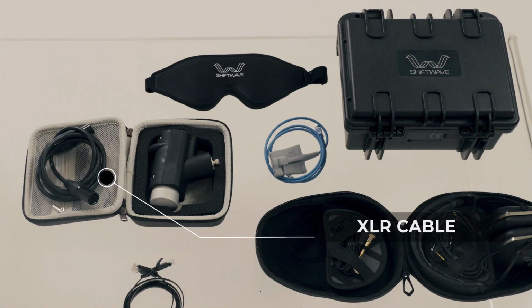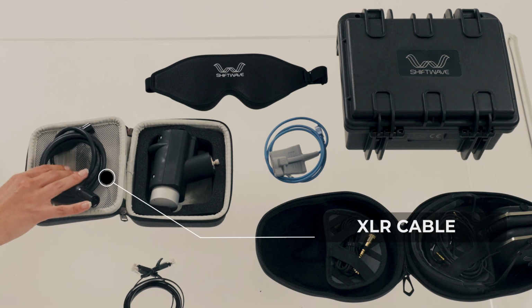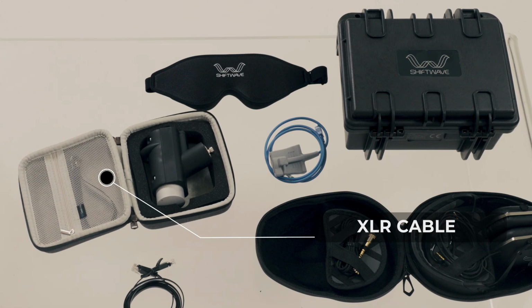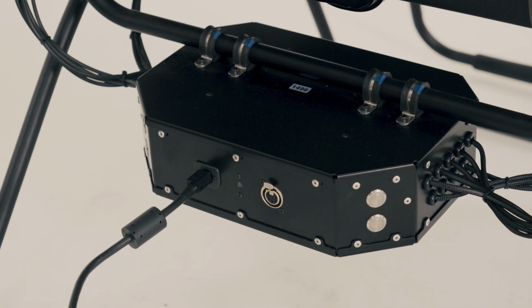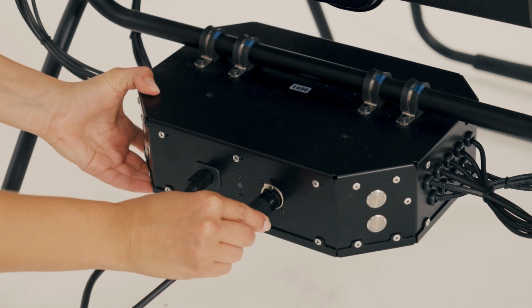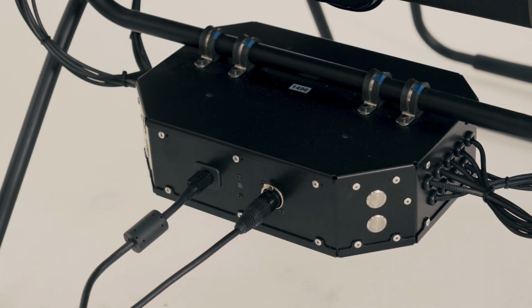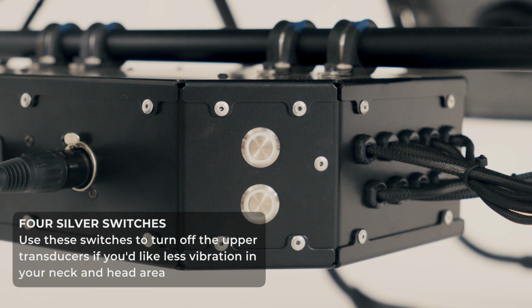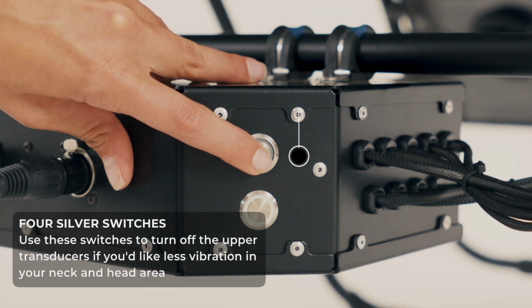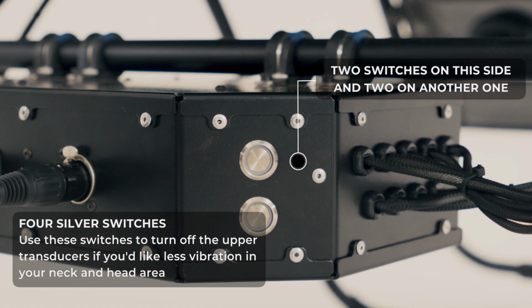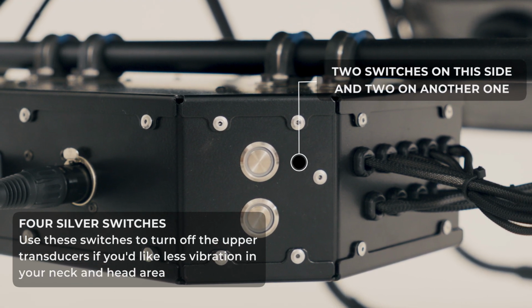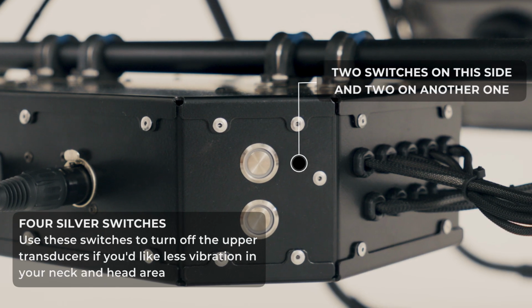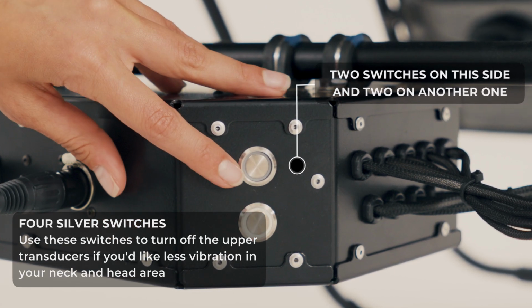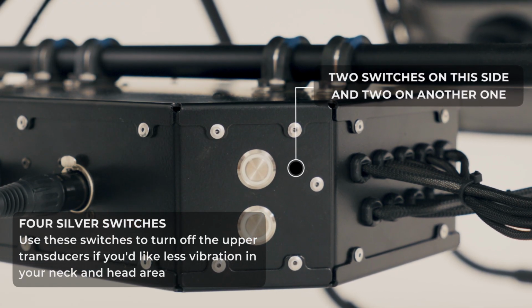Next, you'll open the accessory pack and locate the black XLR cable. It's rounded on both ends. Align the top notch facing upward and insert it into the port on the chair until it clicks. On the back of the black box underneath the chair are 4 silver switches that let you turn off the top 4 transducers if you prefer less vibration in your neck and head area. Useful for shorter users or personal preference.